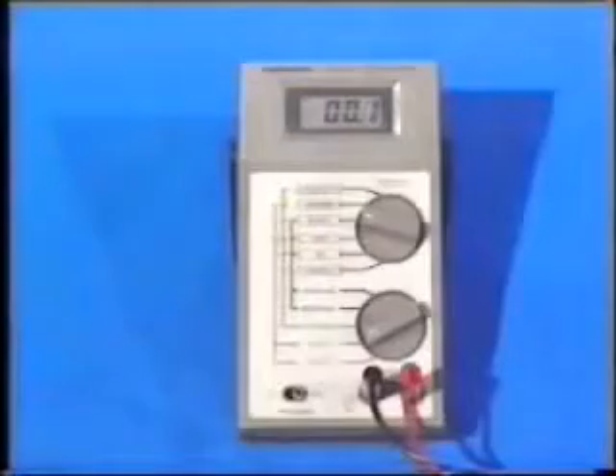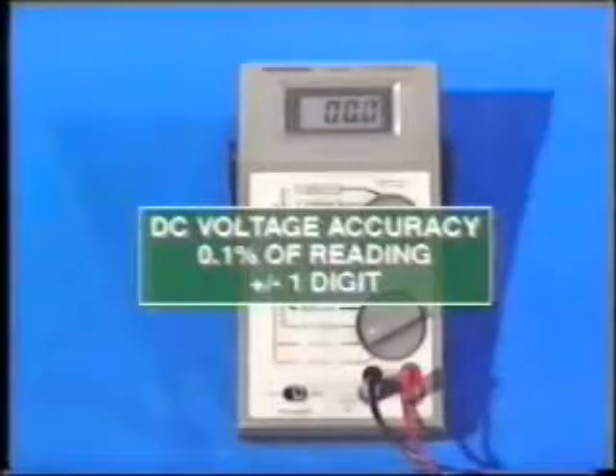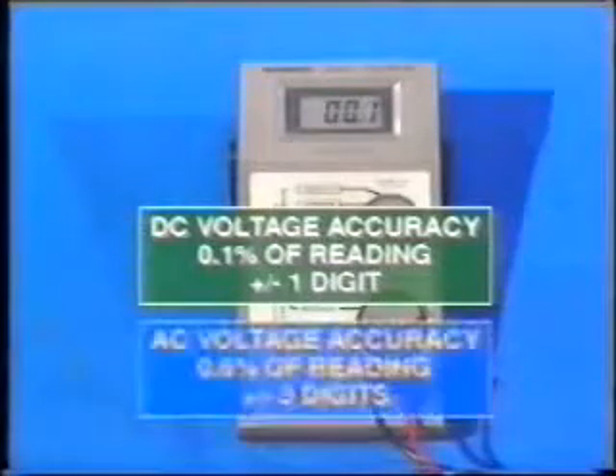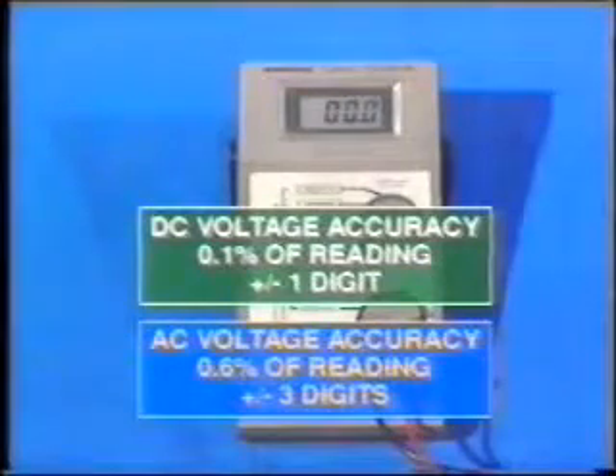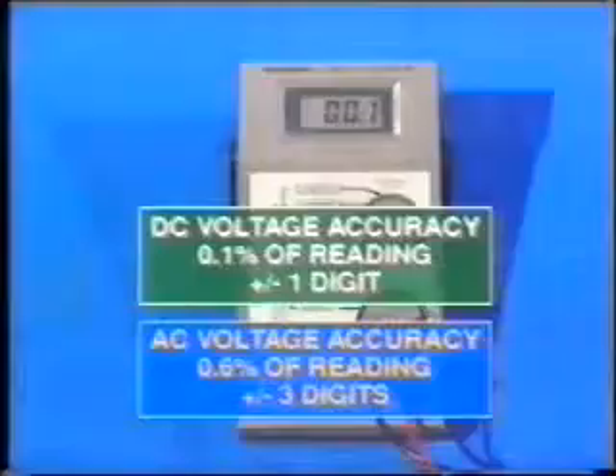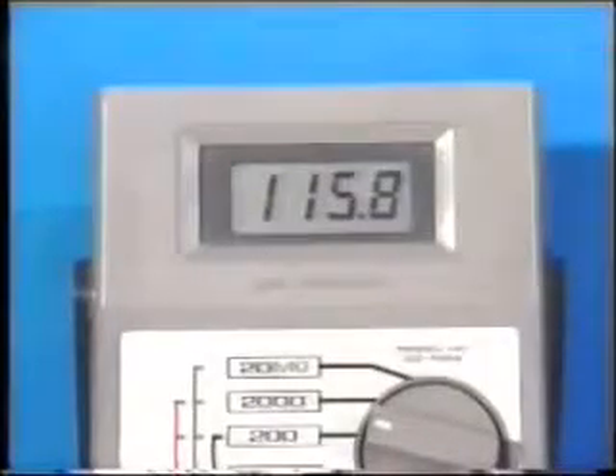When using a DMM, be aware that the accuracy of measurement may not be the same for different types of measurements. For example, with this meter, the specification indicates a DC voltage accuracy of 0.1% of the reading, plus or minus 1 digit. However, if we select this instrument to measure AC voltage, then the specified accuracy falls. The tolerance for error is now 0.6% of the reading, plus or minus 3 digits. This is for a frequency within the normal range of 45 Hertz to 2 kilohertz. Note that an error of, say, 3 digits on the scale has less significance on a full-scale reading than one at the lower end. Bear in mind when interpreting test results that the margin of error may be plus or minus.